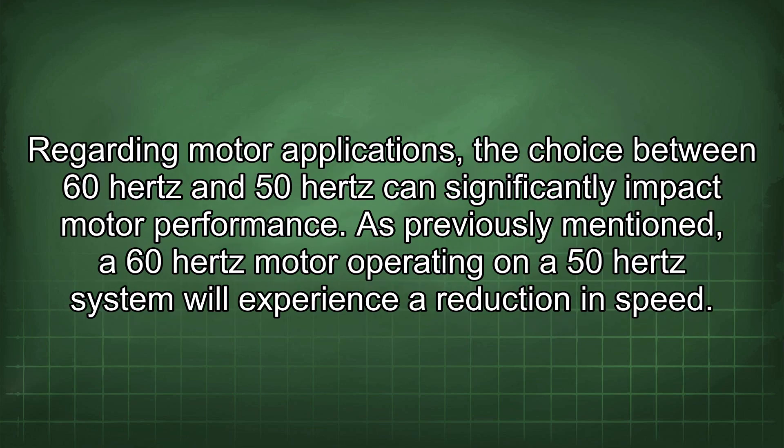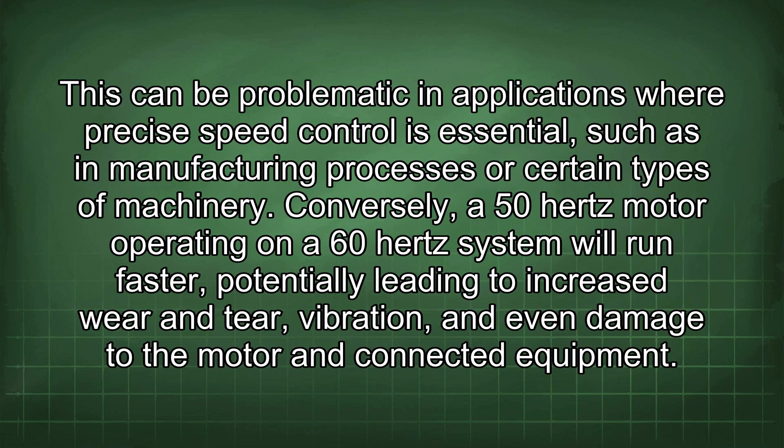Regarding motor applications, the choice between 60Hz and 50Hz can significantly impact motor performance. A 60Hz motor operating on a 50Hz system will experience a reduction in speed, which can be problematic in applications where precise speed control is essential, such as in manufacturing processes or certain types of machinery. Conversely, a 50Hz motor operating on a 60Hz system will run faster, potentially leading to increased wear and tear, vibration, and even damage to the motor and connected equipment.